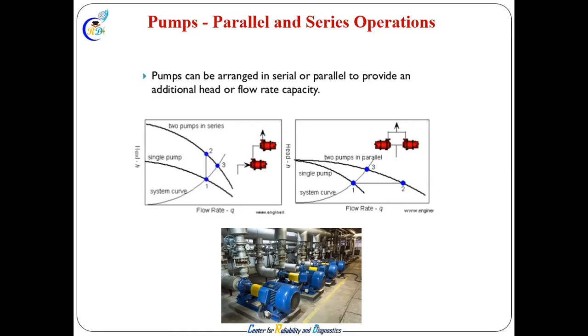Be careful, because here the system curve will determine how much more you'll get. You will get a little more than what you got with one pump. So in between, maybe half, you can say half. So it is not double, you get 1.5 times the flow.